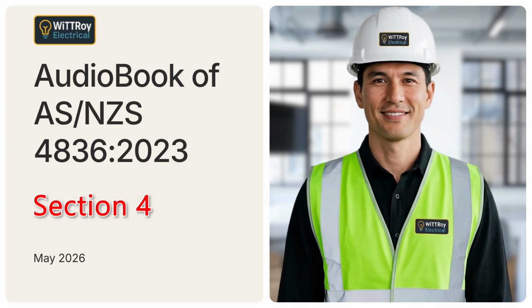Safety or information tags should be fitted where needed. Barriers, barrier tape, or other suitable methods should be used to keep unauthorized people out of the work site. Relevant people must be told that the work is not complete. They must also be told about any potential hazards. Precautions must be taken to confirm that the electrical installation or equipment cannot become energized unexpectedly.